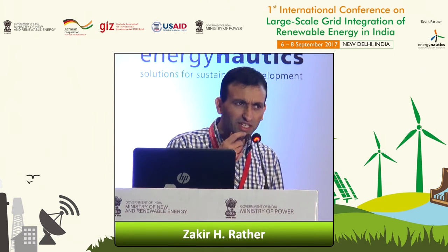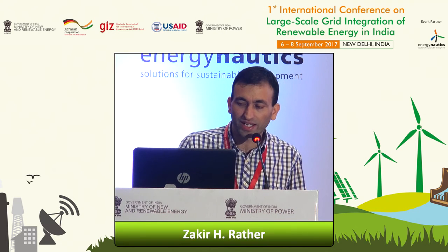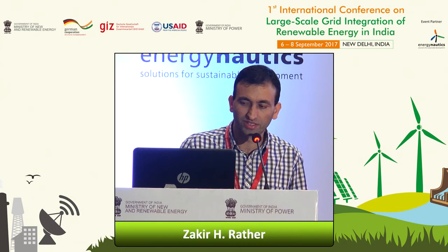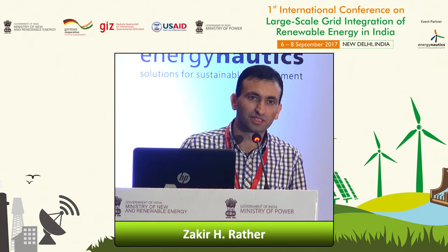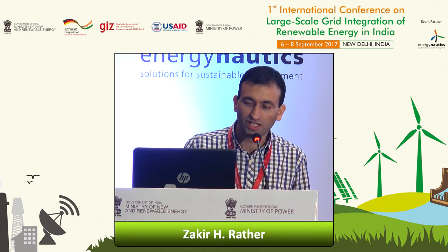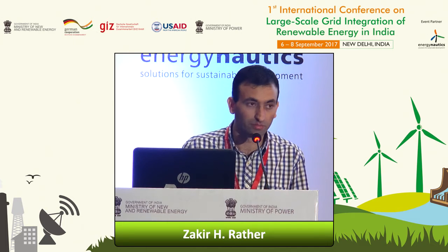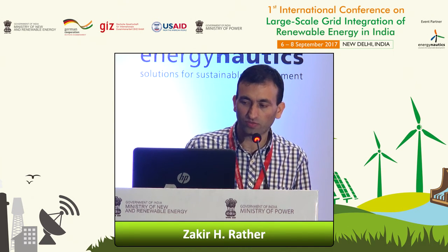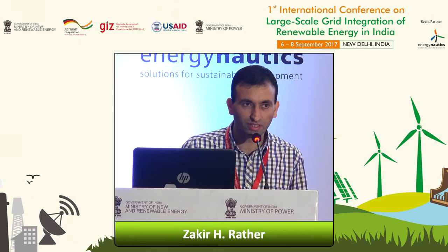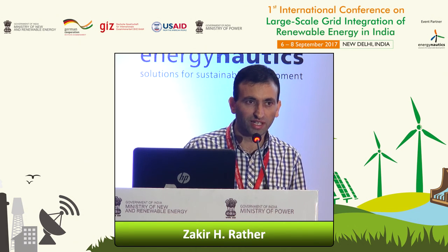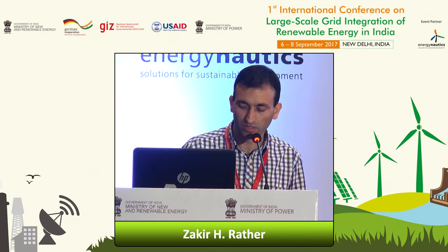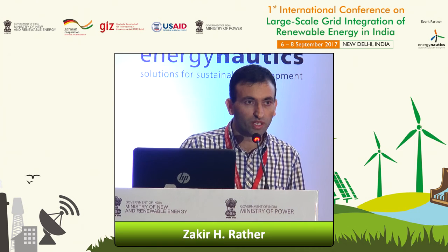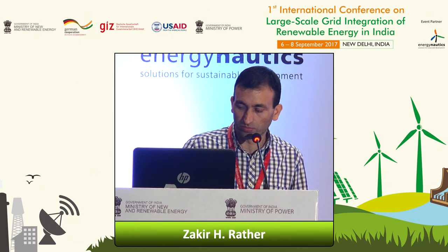On the right side, this is a small study we did to see how the response of a wind farm differs when we change the modeling approach. It is a very simple equivalent model we designed with a number of parallel turbines, parallel machines, and parallel transformers, and then we compared it with a detailed wind farm of 100 megawatts. If you see here, the response to the fault is different, because we didn't capture the voltage difference that will be seen by different wind turbines in a wind farm. We just took the parallel combination of machines and transformers. That was not captured. At the same time, the wake effect and other issues were not captured. So we always need to consider those when we try to form an equivalent model of the wind power plant.